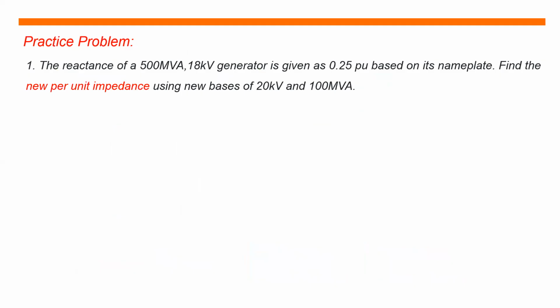So let's have practice problem number one. The reactance of a 500 MVA, 18 kilovolt generator is given as 0.25 per unit based on its nameplate. Find the new per unit impedance using new bases of 20 kV and 100 MVA.